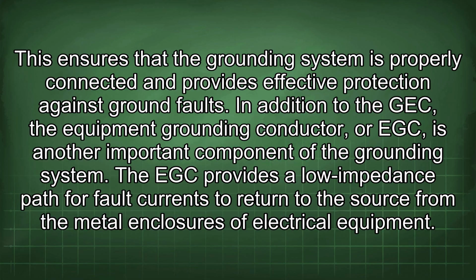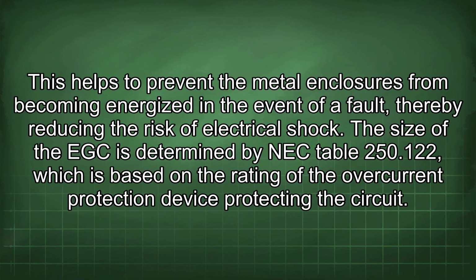In addition to the GEC, the equipment grounding conductor, or EGC, is another important component of the grounding system. The EGC provides a low impedance path for fault currents to return to the source from the metal enclosures of electrical equipment. This helps to prevent the metal enclosures from becoming energized in the event of a fault, thereby reducing the risk of electrical shock.